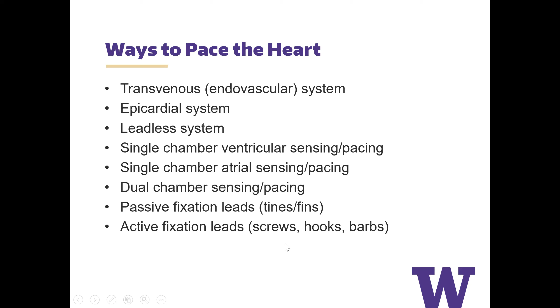So pacing leads can be bipolar or unipolar. Obviously, this is the electronics of this topic. A bipolar lead has 2 conductor coils and 2 electrodes in contact with the myocardium, and so it generates a very small current loop. It's about 2 to 3 centimeters to complete that circuitry. A unipolar lead has 1 conductor coil and 1 electrode in contact with the myocardium, and the current flows from that through the chest to the pulse generator. That creates a very large loop of current because it has to progress from the heart up to the chest where the generator is.